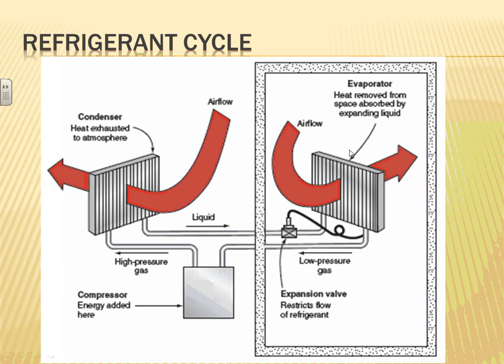So you collect the heat through the evaporator, and the liquid changes into the so-called low pressure gas. Then you pressurize that gas through the compressor and pass this high pressure gas through the condenser. The condenser has big fans blowing the air right through these coils. When the air goes through the coils, it removes the heat that has been collected from the place that you need to cool, all the way out. It changes from high pressure gas into liquid, and it continues the whole cycle. Did I do it right, Dave?